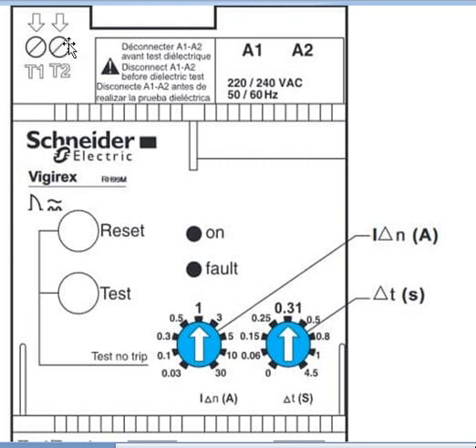So on the top there are two more terminals, T1 and T2. These terminals are going to be used with the toroid. The toroid is used to measure the leakage current in the circuit. Normally the vector sum of the current will be 0. If you are using it for three phases, the vector sum will be 0 in normal operation.